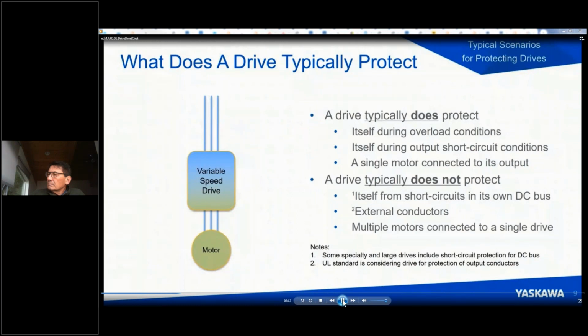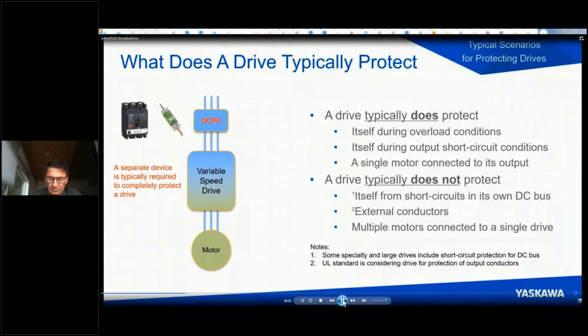Another thing that happens to be going on with UL, which is a future thing and not yet a UL listed situation, is that they are considering the drive for being UL listed for protection of output conductors, but this is work in process. This is not available yet. So often, a separate device is typically required to completely protect the drive. Generically, we refer to those devices as overcurrent protective devices, or OCPD for short, which is typically a circuit breaker or a fuse.